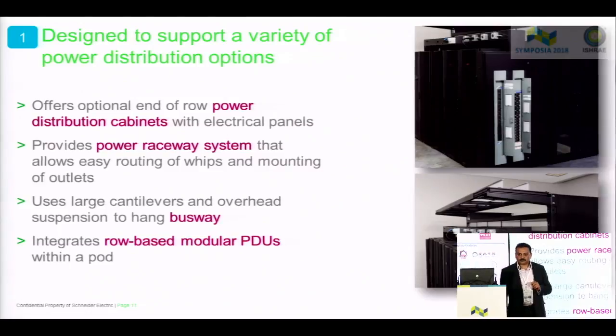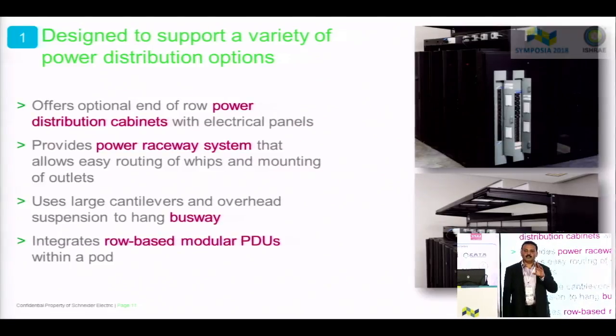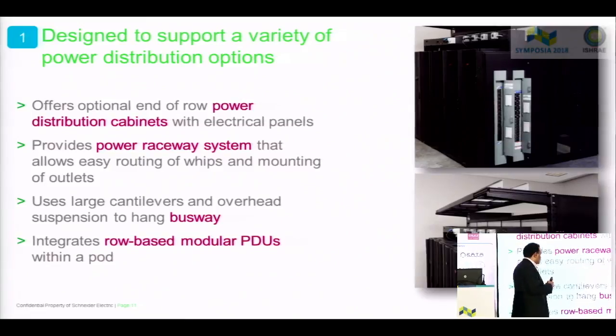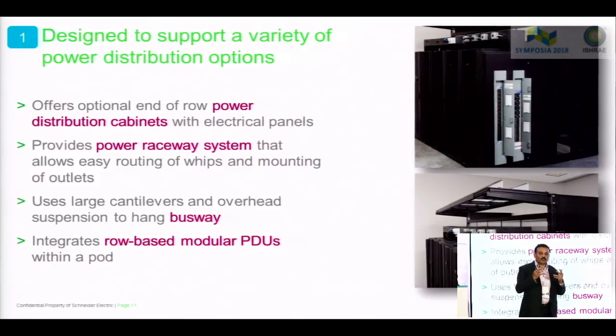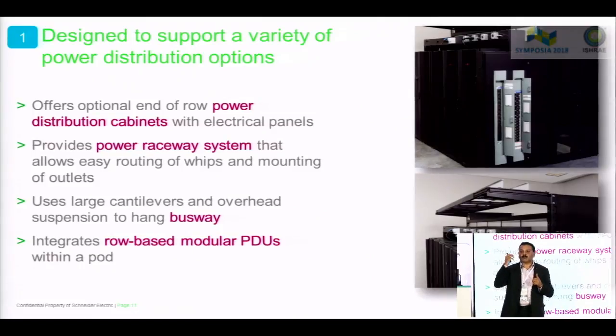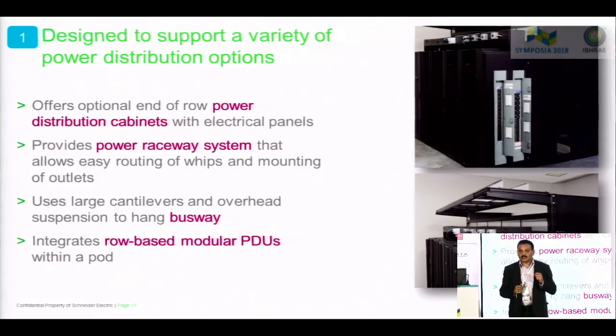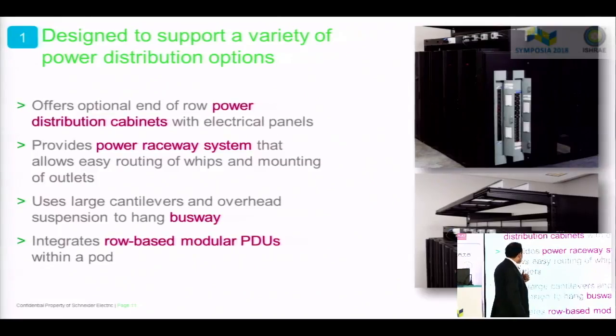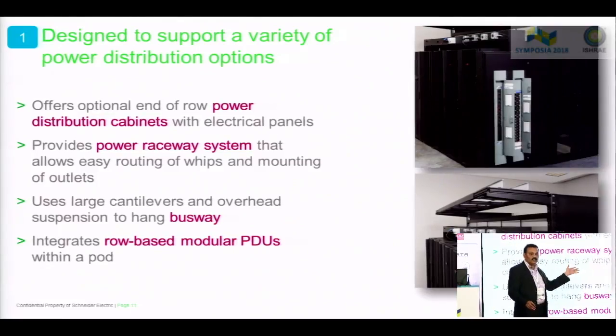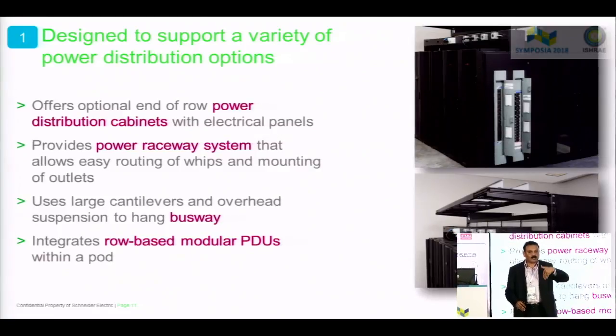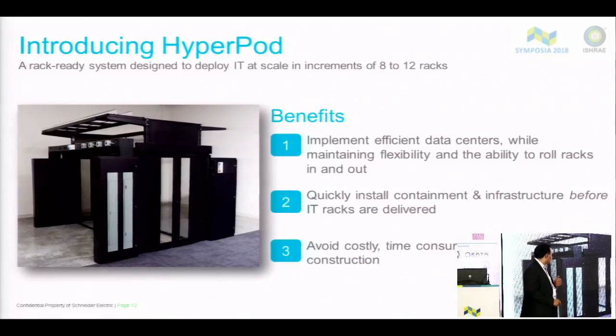Let's look at the power. It's compatible with connecting either a row-based power solution, which sits as the power distribution at the end of the row, or within the row, in-row power distribution. It can also take care of busway systems at the top of the racks. More importantly, through flexible and extended cantilever systems, you can mount all the cabling here. You don't need ceiling suspended cable trays for a data center, and the cables are not required to be taken from below the false floor. This is a self-contained system in its totality. So lots of flexibility is available in this.